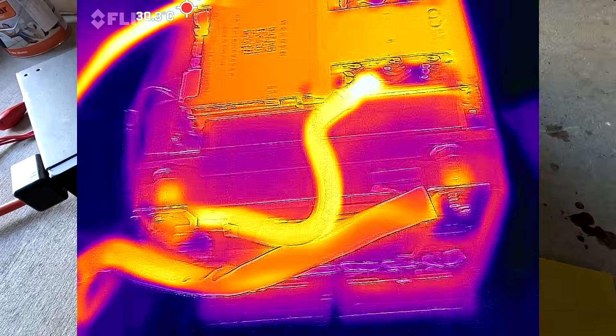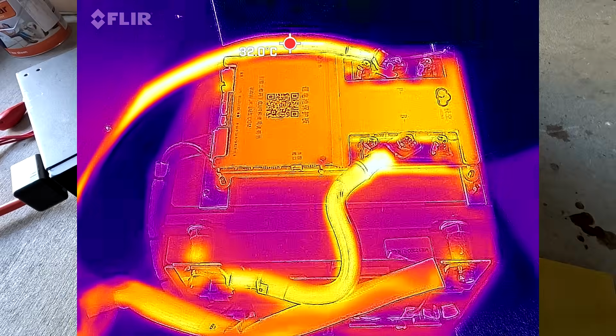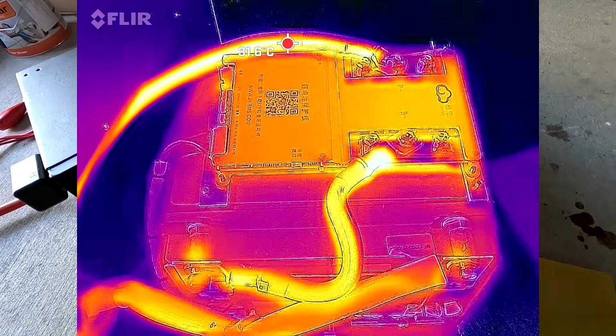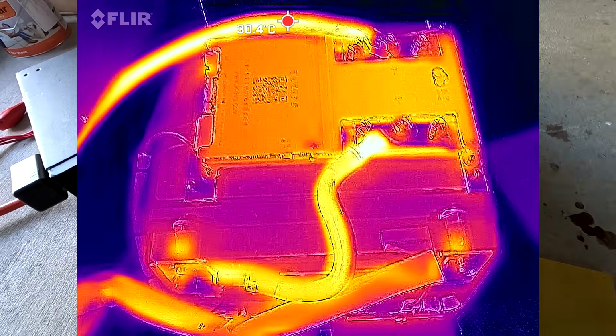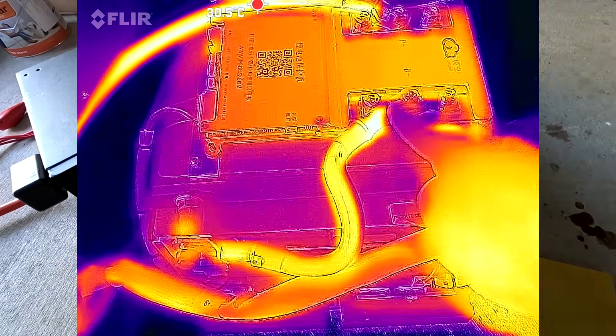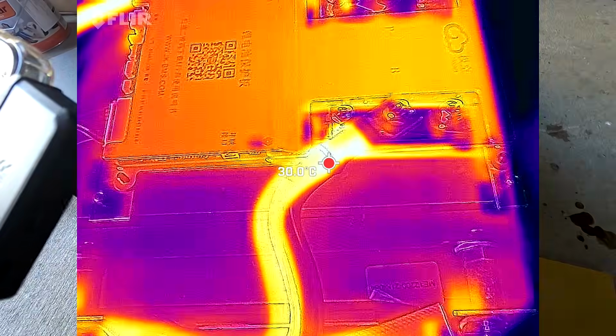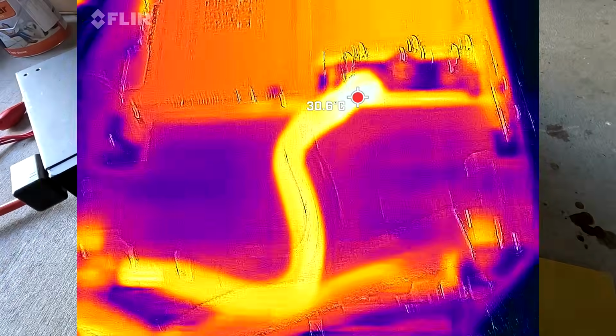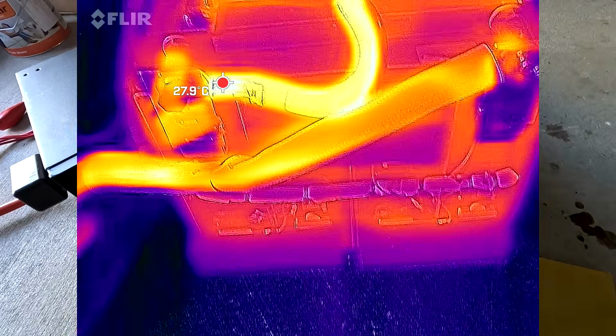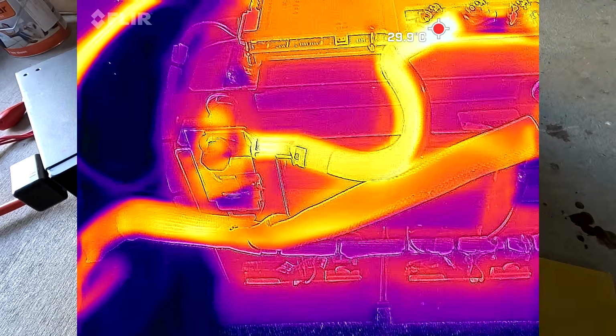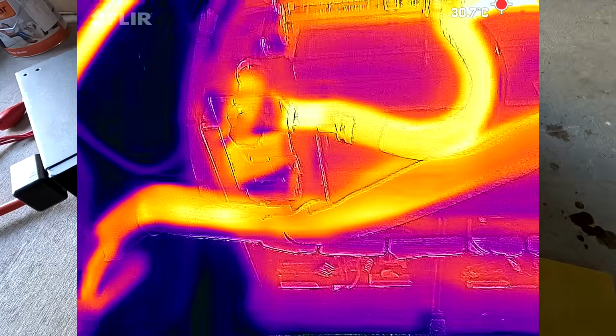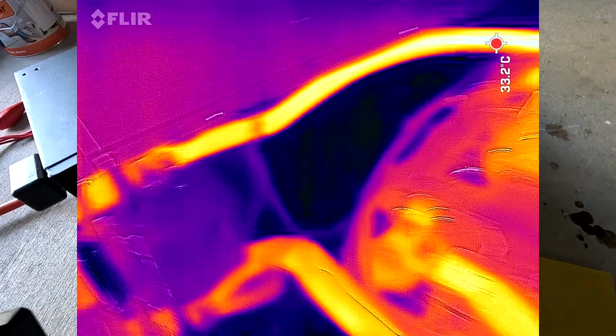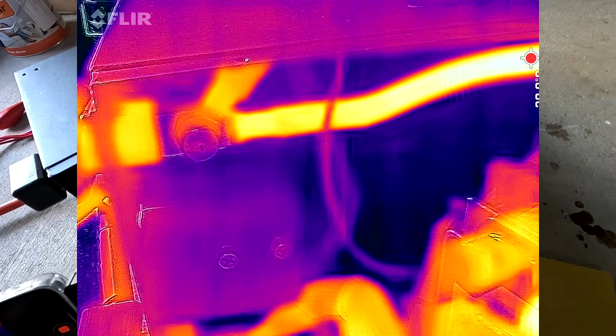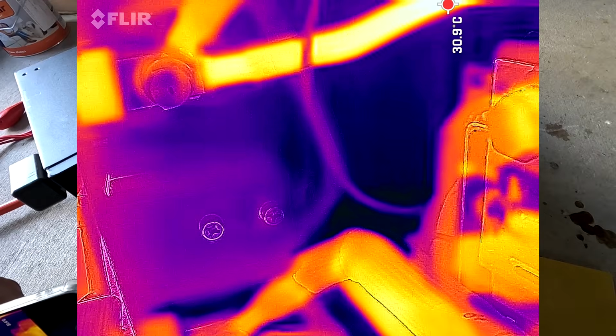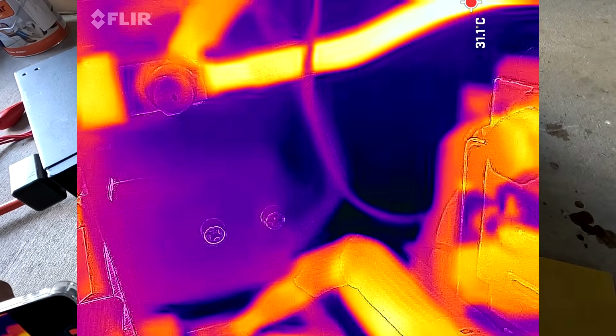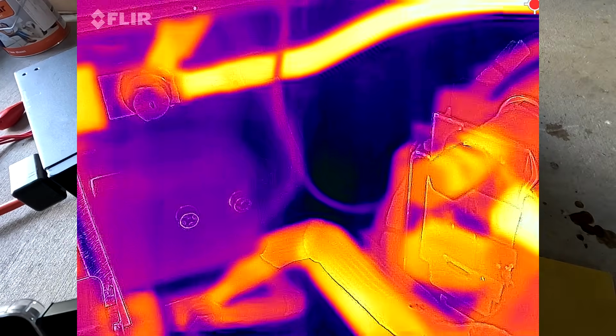So there we are, that's the infrared camera, and we see 32 degrees on the cable. Nothing much on the BMS, there's a bit of heat building up here on this ring lock, but we're only talking about 30 degrees. The battery itself is fine. Here as well, these are the ring locks and the cable, the 2-gauge wire, and there should be nothing happening inside this box. It's the cable again, 30 degrees. No, that's all fine.